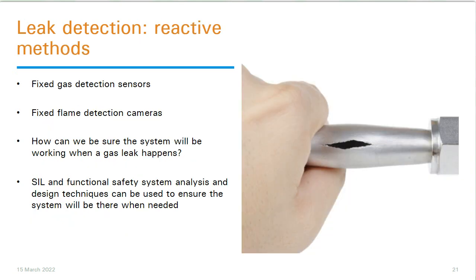Furthermore, there are leak detection technologies that can help us to reactively tell us that there's been a problem. If we have a pipe burst, as in the photograph here, hopefully a fixed gas detector close to that pipe will be able to sound an alarm and tell us reactively that something has gone on. That's not necessarily part of a proactive maintenance routine. It's reacting to a problem, a situation after it's taken place. And there's a number of technologies such as fixed flame detection or fixed gas detection systems that are ideal for that particular purpose.